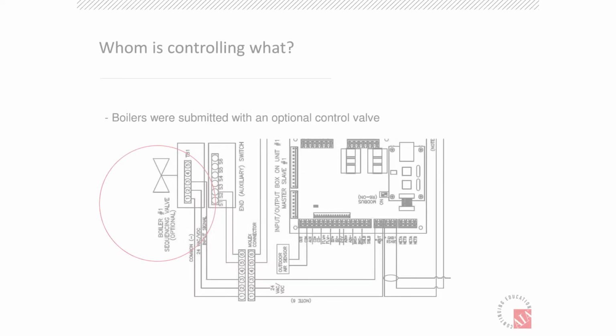I was brought in - I wore many hats. I wasn't commissioning this job. I was brought in for a condition assessment after we had some control issues on the boilers. So I started going back and reviewing all the sequences and submittals before I went out to the site to see what was going on, and I found this optional control valve. The complaint was actually that our boilers keep tripping off on high water temp, okay?